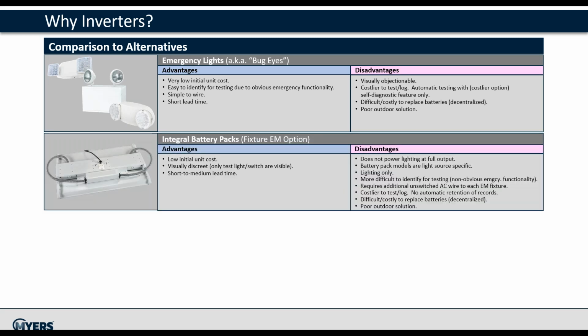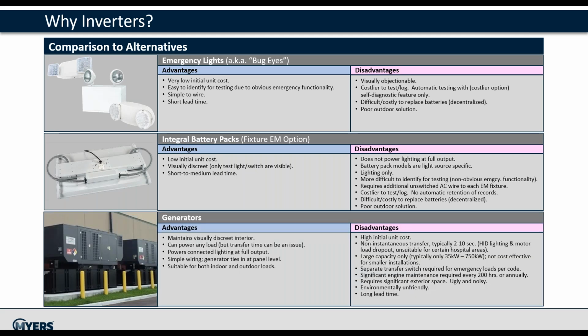Integral battery packs have advantages of low cost, visually unobtrusive, with only the light and test switch seen through the ceiling, and short to medium lead time. Disadvantages are it does not provide full output, so more fixtures are required for emergency. It's not available in all lighting fixtures. It can only be used to power lighting. It requires an additional unswitched AC wiring for sensing. Testing and logging are non-automatic and costlier. It's costly to replace the batteries, and it's a poor outdoor solution.